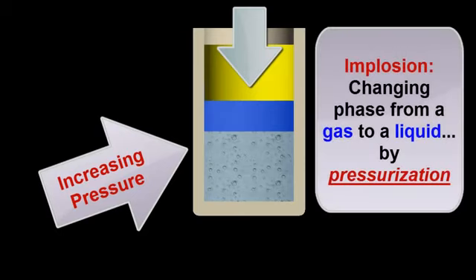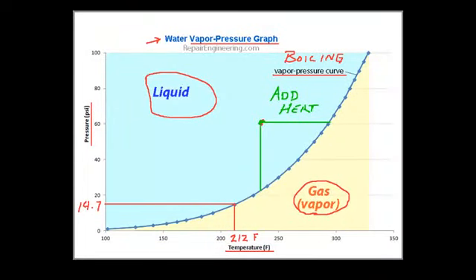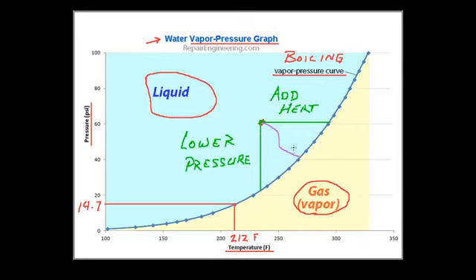This rapid collapse, also called an implosion of gas bubbles under pressure, is the basis for understanding how cavitation damage is caused. Going back again to the vapor pressure graph, we have seen that water can be caused to boil by either adding heat or by lowering its pressure. Obviously, it's also possible to cause the water to boil by any combination of changes to its temperature and pressure.